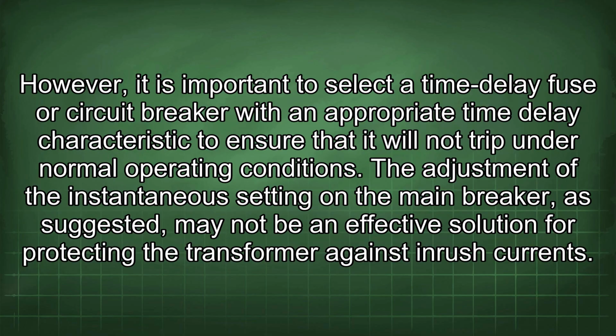However, it is important to select a time delay fuse or circuit breaker with an appropriate time delay characteristic to ensure that it will not trip under normal operating conditions. The adjustment of the instantaneous setting on the main breaker, as suggested, may not be an effective solution for protecting the transformer against inrush currents.